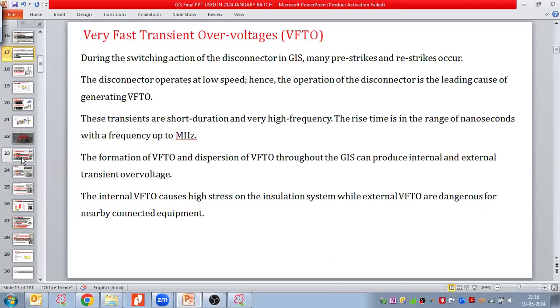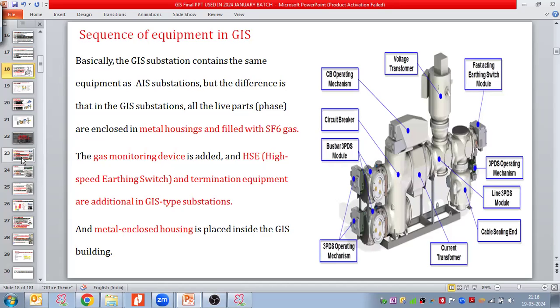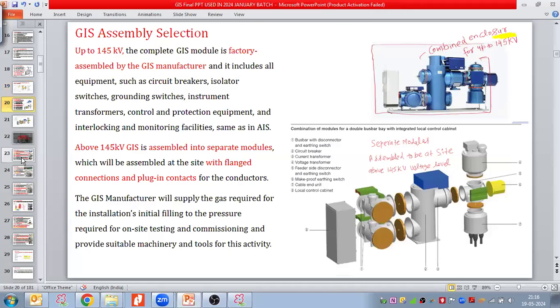So it is generated between the disconnectors and the bus bar due to the disconnector operations, because it is very close to the bus bar. So a re-strike occurs between the disconnector's fixed and moving contact, and due to that re-strike, VFTO is generated in GIS type switchgear substations. So we discussed the sequence of equipment, and then we discussed the assembly selection as well yesterday. So what is the concept for the assembly selection?